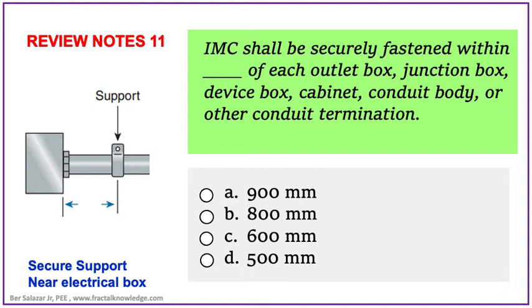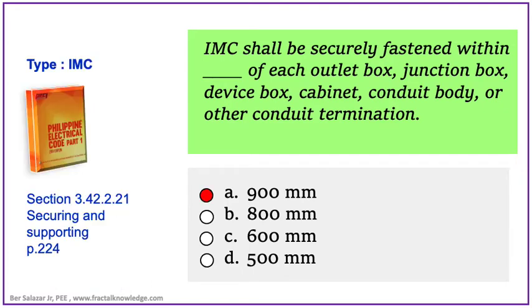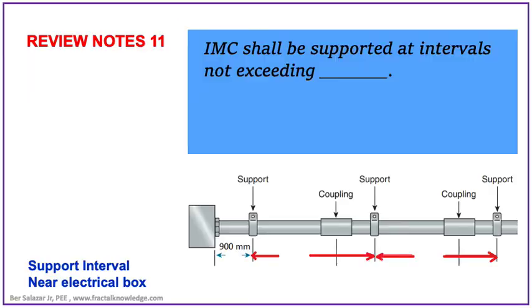Here is another question regarding IMC: IMC shall be fastened within what distance from its electrical box, junction box, cabinet, or near its termination? Drawings are presented for visualization but during board exam they are not there. Is the answer 900 mm, 800 mm, 600 mm, or 500 mm? The answer is letter A: 900 mm near any electrical box, outlet box, junction box, or near termination. You can check it in PEC section 3.42.2.21, page 224, for IMC securing and supporting.